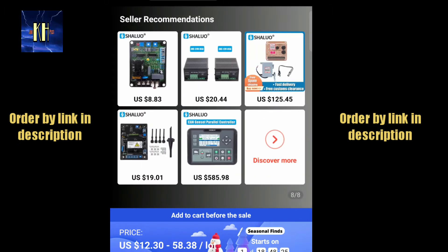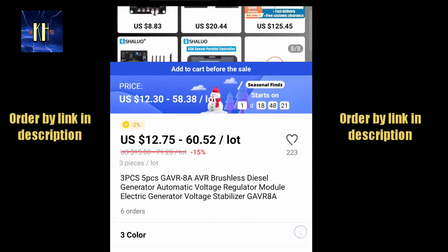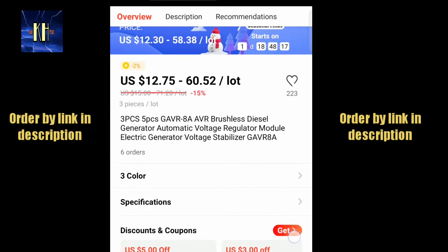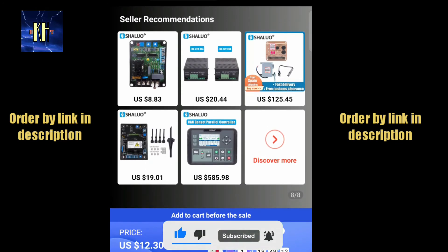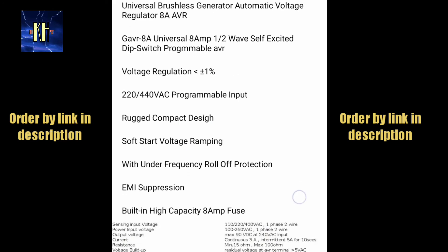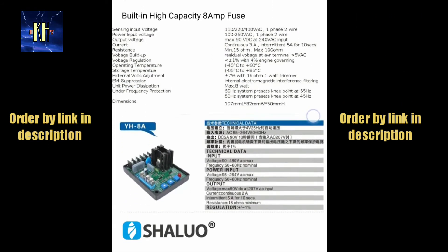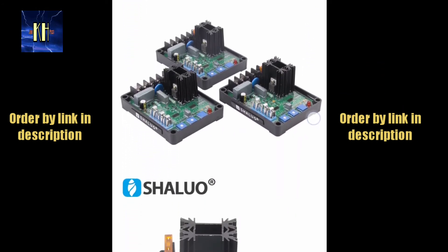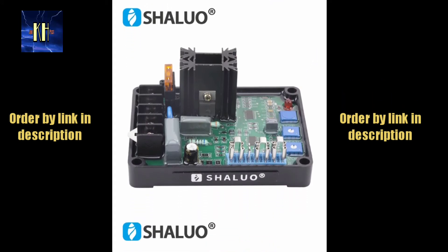Built-in high capacity 8 Amp fuse. Sensing input voltage: 110/220/400VAC, 1-phase 2-wire. Power input voltage: 100 to 260VAC, 1-phase 2-wire. Output voltage maximum: 90VDC at 240VAC input. Current: continuous 3A, intermittent 5A for 10 seconds. Resistance: minimum 15 Ohm, maximum 100 Ohm.